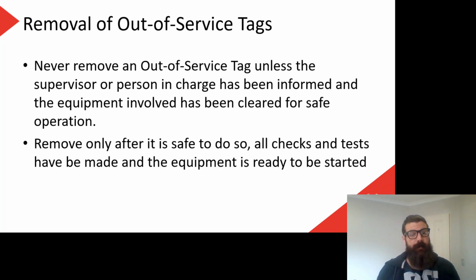Removal of out of service tags. Never remove an out of service tag unless the supervisor or person in charge has been informed and the equipment involved has been cleared for safe operation. In most cases it would just be you anyway by yourself, but it is what it is. Remove only after it is safe to do so and all the checks and tests have been made and the equipment is ready to be started. Remember that once you remove that isolation and remove the tag, anyone can come along and switch that on at any time. So we definitely don't take that off until we are absolutely ready to turn that on, and that nothing unsafe is going to happen if we do turn it on.